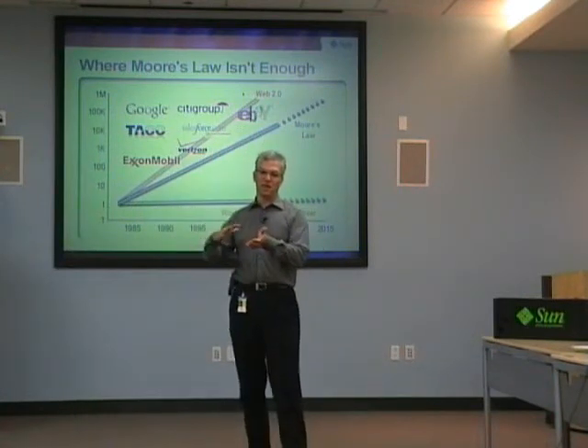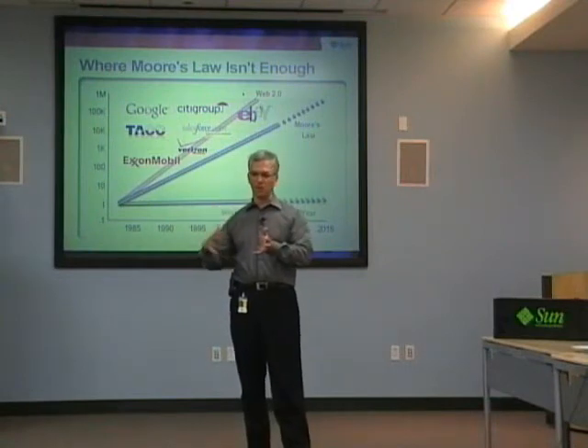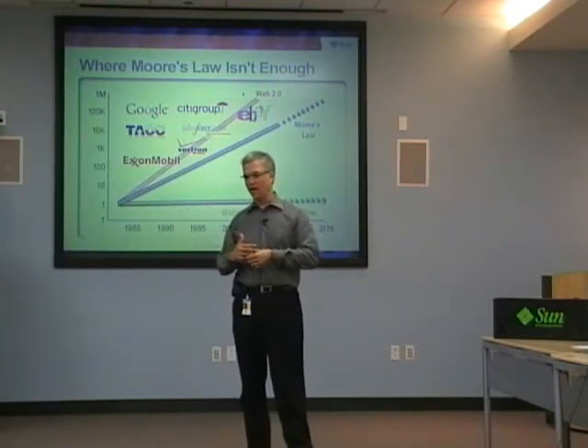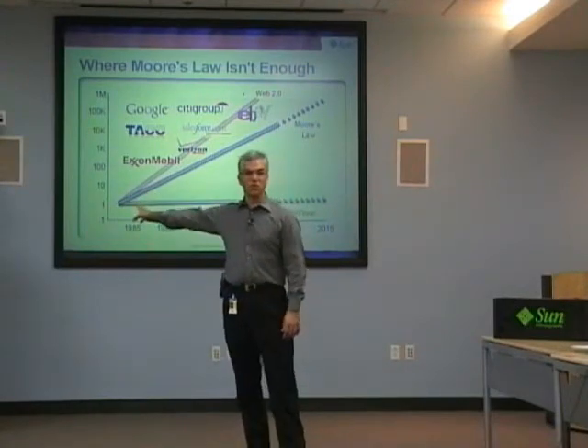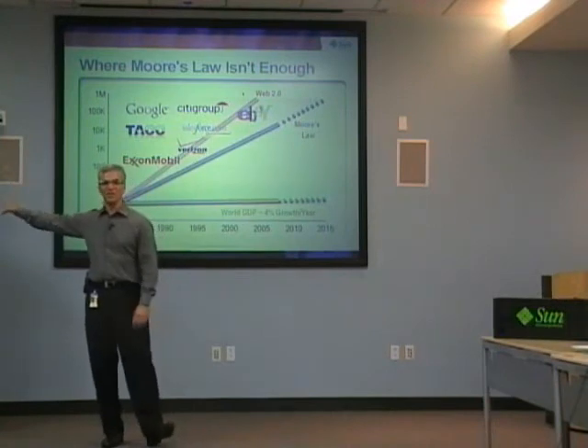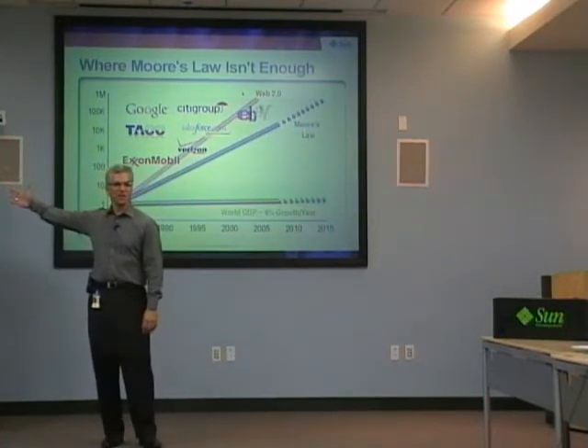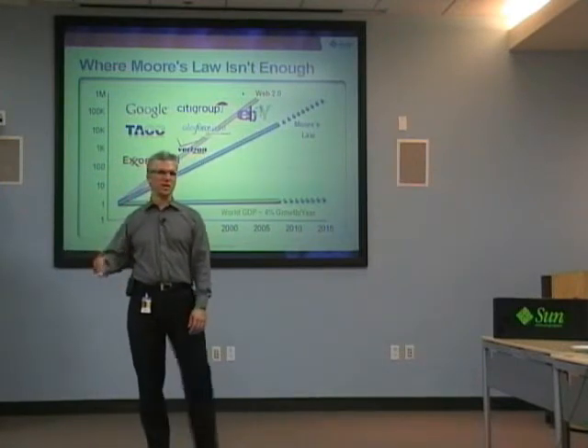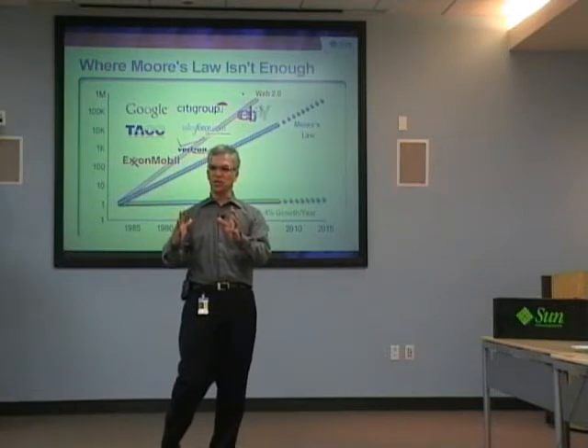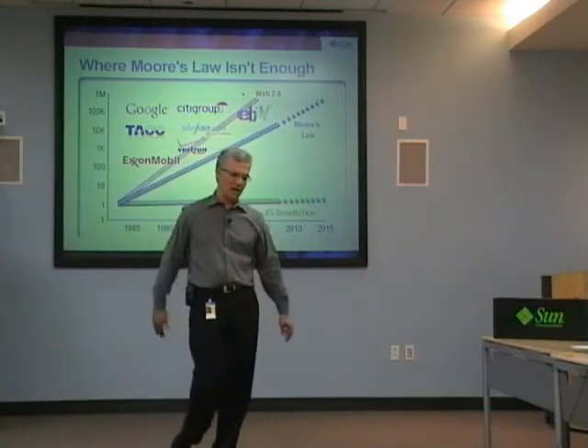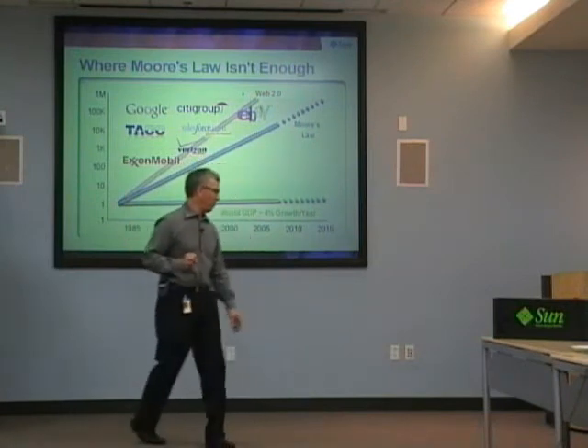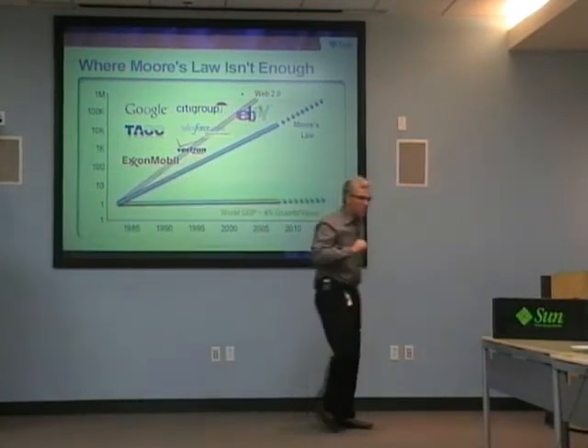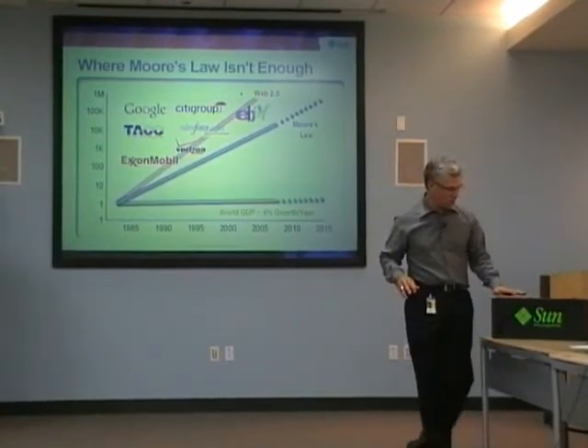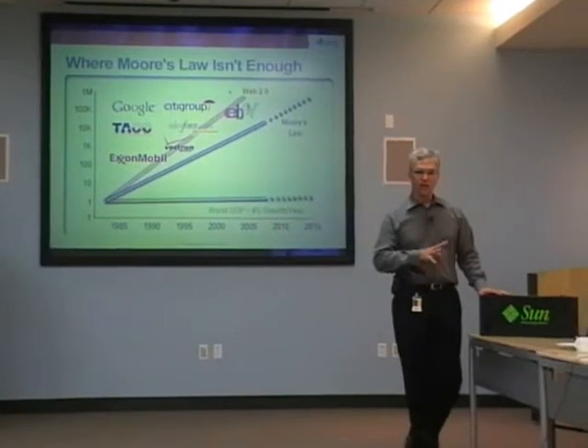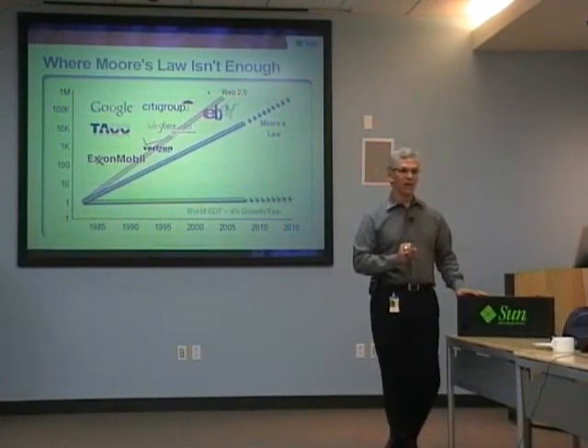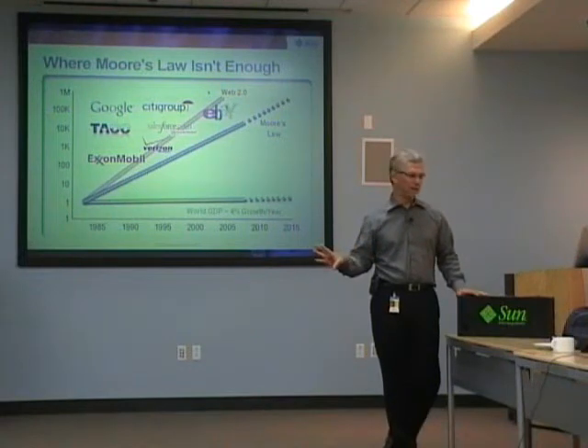Essentially what's happening is power densities, for good reasons, are going through an enormous acceleration. You look at racks of equipment here - these are very fuel efficient designs, so to speak. But there's 10,000 watts accumulated in that rack, and it's going to go to 15, 20, and 25,000 because the density lets you get superior connectivity and networking among those components, even when you drive them with very efficient components. So that's where we basically ended up. The most important single assumption here is that this is a space designed for machines, riding on the trends towards lights-out management and virtualization.